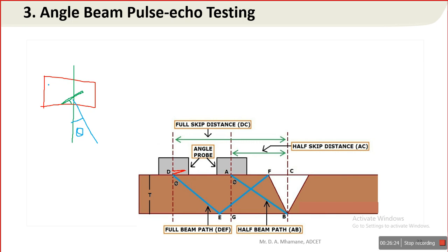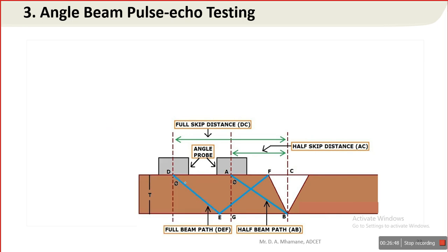This is the probe, and this is the piezoelectric crystal which transmits the ultrasound, and when that crystal is placed at a predefined angle, it gives us the wave at a predefined angle. So this is the angle probe.